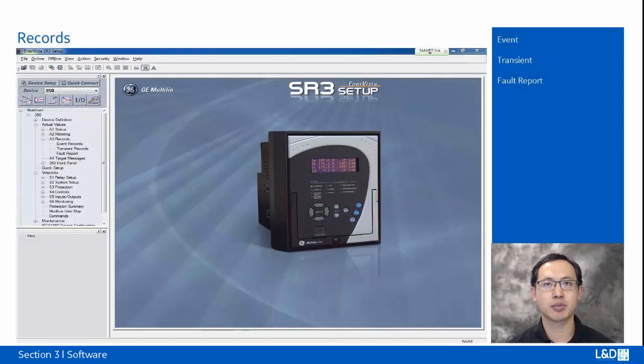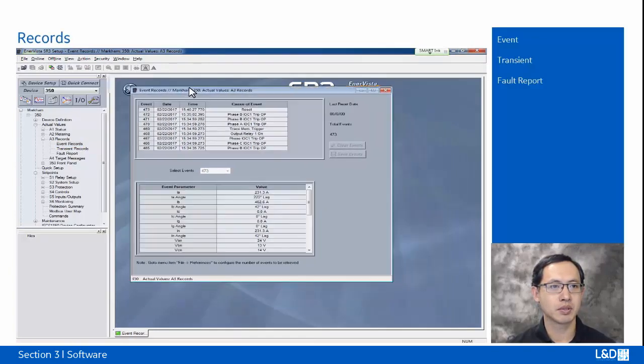3 series relays provide 3 types of records: event records, transient records, and fault report. To launch the records, we can go to the actual values and click A3 to click on each item: event records, transient records, or fault records. Or we can go to the shortcut toolbar and click the shortcuts for the event records or the transient records, also called waveform records. So now let's open the event records and see what happens.